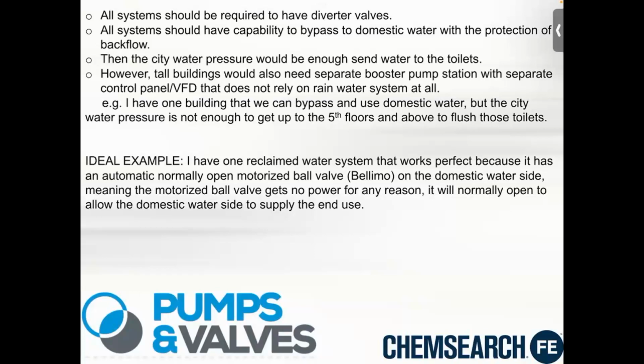The ideal example is a building where it works perfectly because there's an automatic, normally open motorized ball valve. In this case, it's a Belimo brand on the domestic water side. Meaning if the motorized ball valve gets no power for any reason, it will normally open to allow the domestic water side to supply the end use. So that would be ideal if all the buildings were able to do that. You would think they would be.